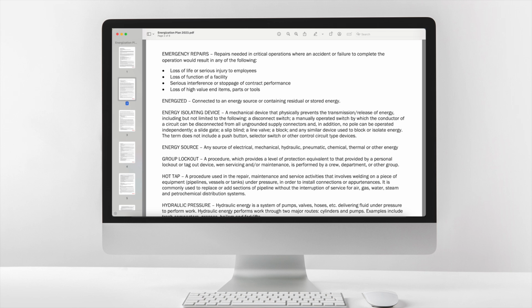Energy isolating device. A mechanical device that physically prevents the transmission or release of energy, including but not limited to the following: a disconnect switch, a manually operated switch by which the conductors of a circuit can be disconnected from all ungrounded supply conductors and, in addition, no pole can be operated independently, a slide gate, a slip blind, a line valve, a block, and any similar device used to block or isolate energy. The term does not include a push button, selector switch or other control circuit type devices. Energy source. Any source of electrical, mechanical, hydraulic, pneumatic, chemical, thermal, or other energy.